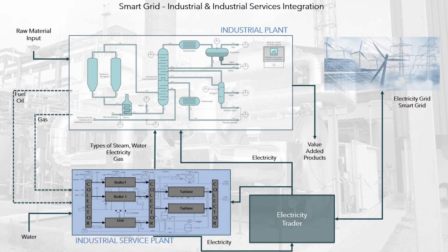The model determines the operational configuration of the plant, by minimizing utility costs, and identifies steam losses as well as inefficient units by comparing the optimal solutions with the current operation. The MILP can accurately represent the topology, and optimize the operation of the real-world system, under different utility demands and abnormal situations in single and multi-period scenarios.